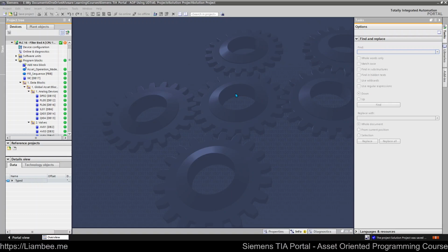And if you do this for all of your assets, instruments, and then the automatic feedback layer for devices such as pumps and valves, then we should be able to completely end-to-end test our entire system with all the program sequences and all that sort of stuff involved as well. And know that when we go to commission the project on site, any issues that arise can only be either on the way into our project or on the way out of our project.